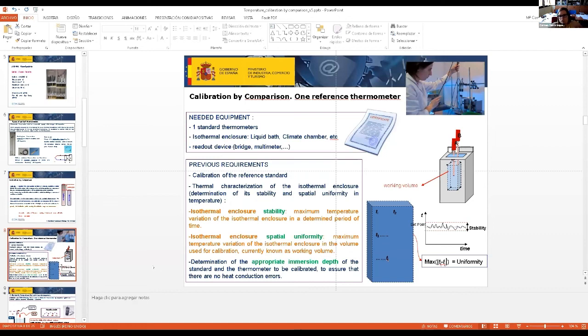So we go to our procedure for the calibration of one thermometer. In this case, we are going to use one reference thermometer. So what do we need? We need one standard thermometer, and also we need an isothermal enclosure. An isothermal enclosure can be a liquid bath or a climate chamber. In this isothermal enclosure is where we are going to generate the temperature for the calibration of this thermometer. And also we need some devices to read the thermometer under calibration and our standard.